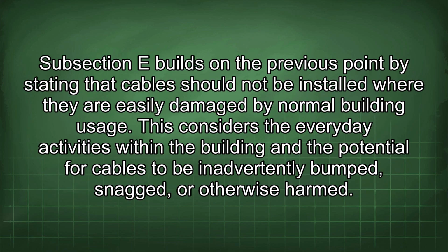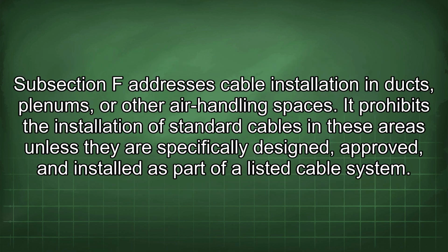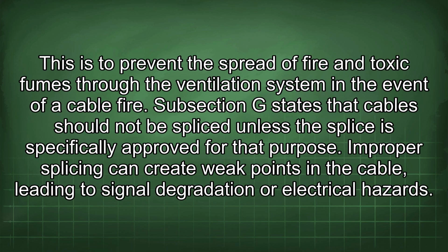Subsection E builds on the previous point by stating that cables should not be installed where they are easily damaged by normal building usage. This considers the everyday activities within the building and the potential for cables to be inadvertently bumped, snagged, or otherwise harmed. Subsection F addresses cable installation in ducts, plenums, or other air handling spaces. It prohibits the installation of standard cables in these areas unless they are specifically designed, approved, and installed as part of a listed cable system. This is to prevent the spread of fire and toxic fumes through the ventilation system in the event of a cable fire.